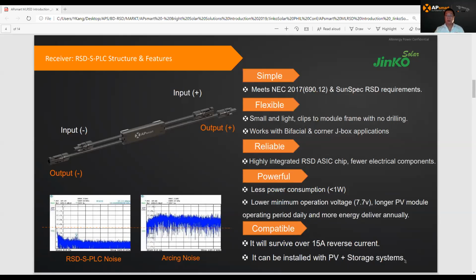Compatible. During our design, we put a bleed down circuit into our device, which means we can survive the reverse current up to 15 amp. This is very critical right now because I had experience, a lot of customers asked me about the PV plus storage system, which is a hybrid system. They highly require some kind of control on the system level from the DC side.